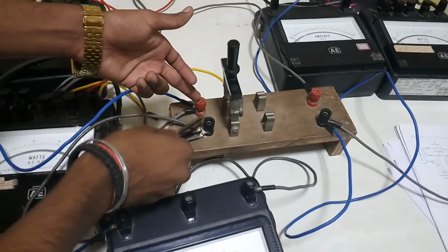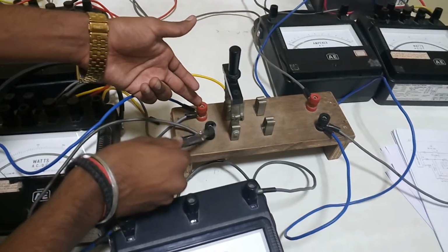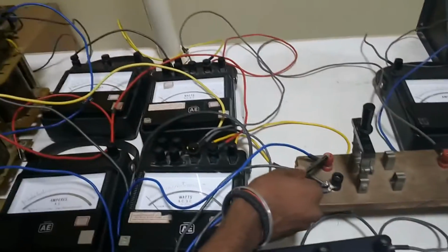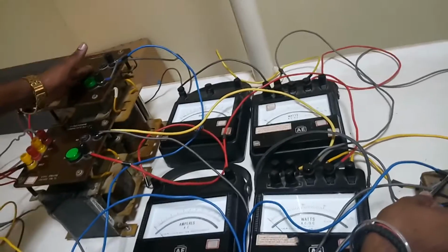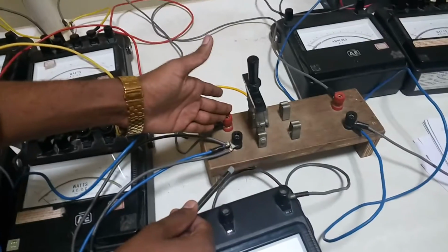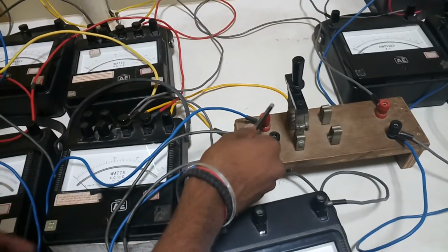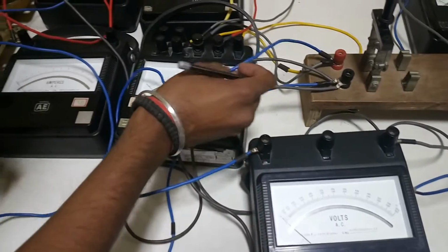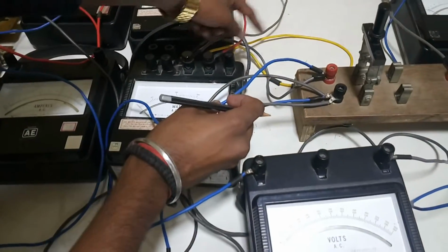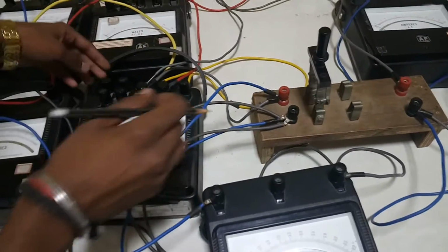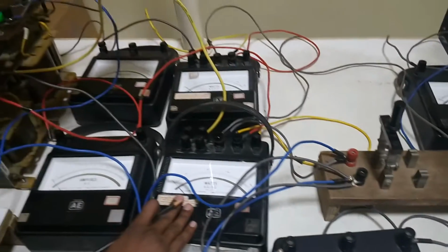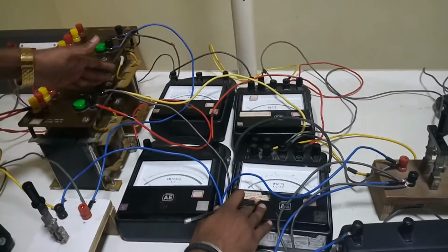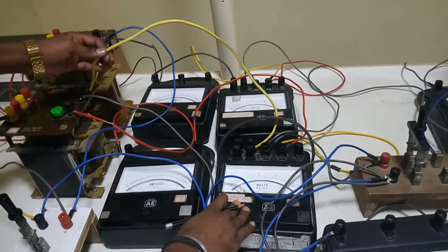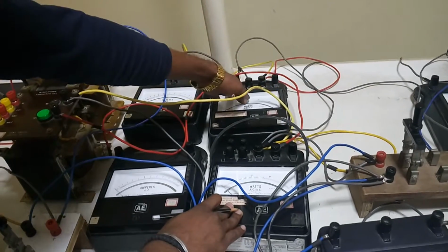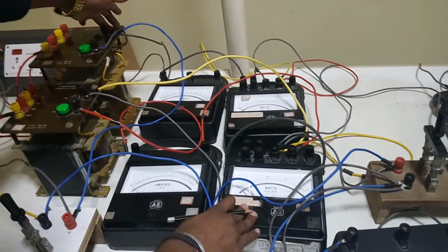Keep in mind the switch positioning should be in this pattern only, because here this is RYB, this is the phase we have considered. So phase should be in line with phase. That's why we have kept the positioning of the switch in this way. Coming to this, L is shorted and given to this. Then V of the second wattmeter is given to the 0 terminal of the 1 kVA. Again, V of the first wattmeter is given to the 2 kVA transformer 0.